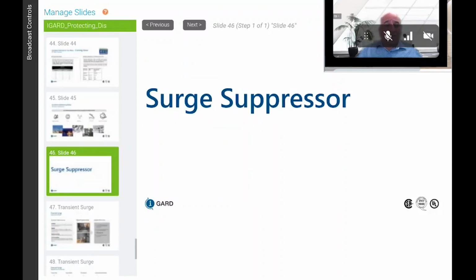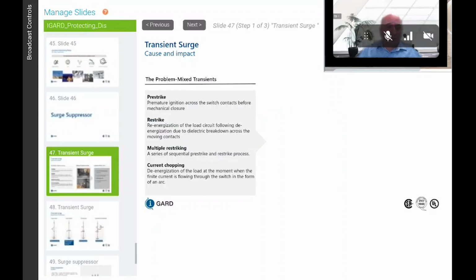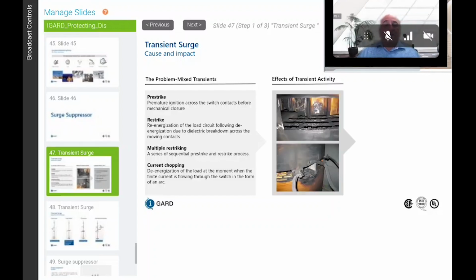The other thing we've introduced is the surge suppressors. Transient surges are caused by, for example, pre-strike of contactors. Try to look at it like this: over the past 10 years, we've tried to make transformers more efficient. To make them more efficient, there are fewer losses, and because there are fewer losses, there's less impedance in the system. Impedance in the system is like a shock absorber. If you remove the impedance, you have no shock absorbers. Every time you switch a circuit on and off, you may have insulation damage, surges that occur because there's no shock absorber there to protect you.